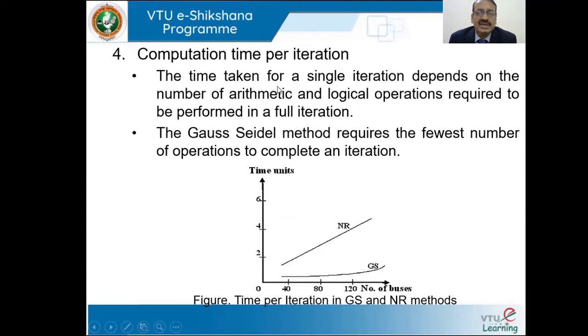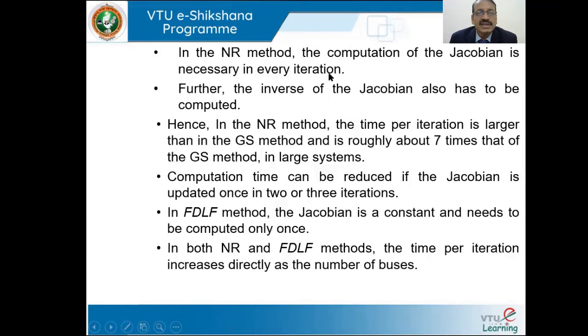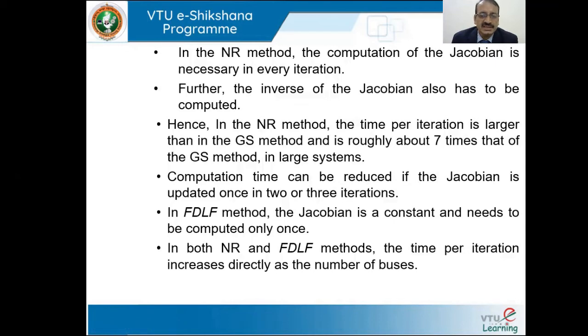Computational time per iteration: the time taken for a single iteration depends on the number of arithmetic and logical operations required in a full iteration. The Gauss-Seidel method requires the fewest number of operations to complete an iteration. In the NR method, the computation of the Jacobian is necessary for every iteration, and the inverse of the Jacobian also has to be computed. Hence, in the NR method, the time per iteration is larger than the Gauss-Seidel method and is roughly about seven times that of Gauss-Seidel in large systems. Computation time can be reduced if the Jacobian is updated once in two or three iterations. In the FDLF method, the Jacobian is constant and needs to be computed only once. In both NR and FDLF methods, the time per iteration increases directly as the number of buses.